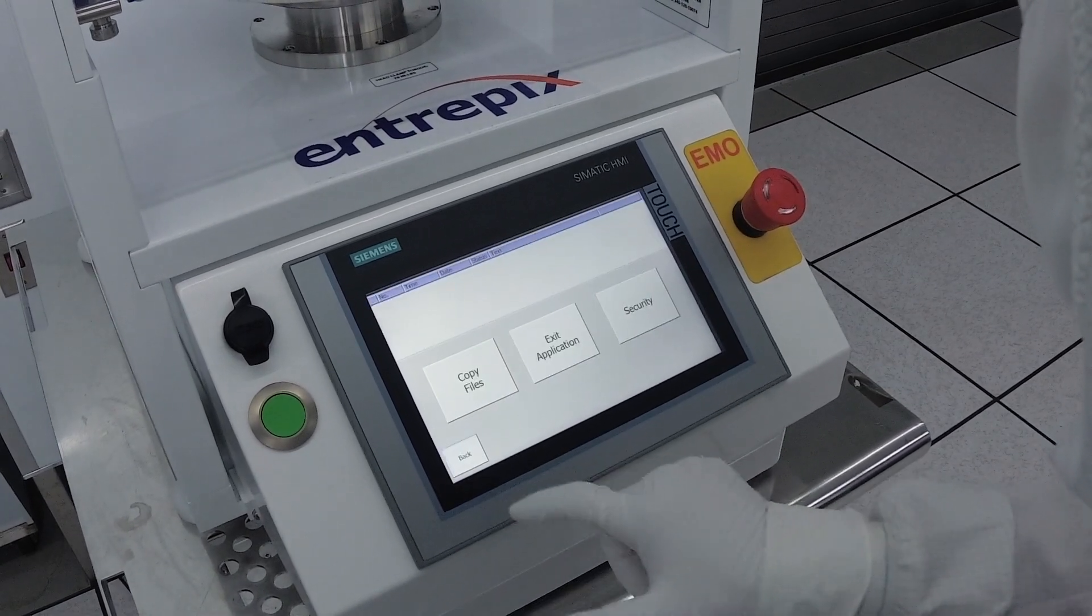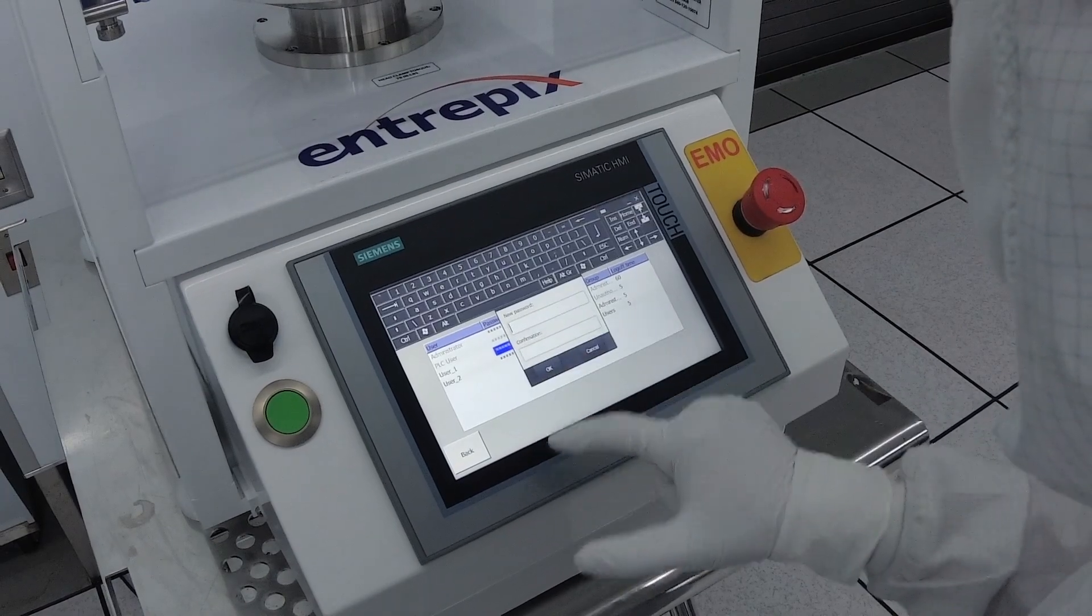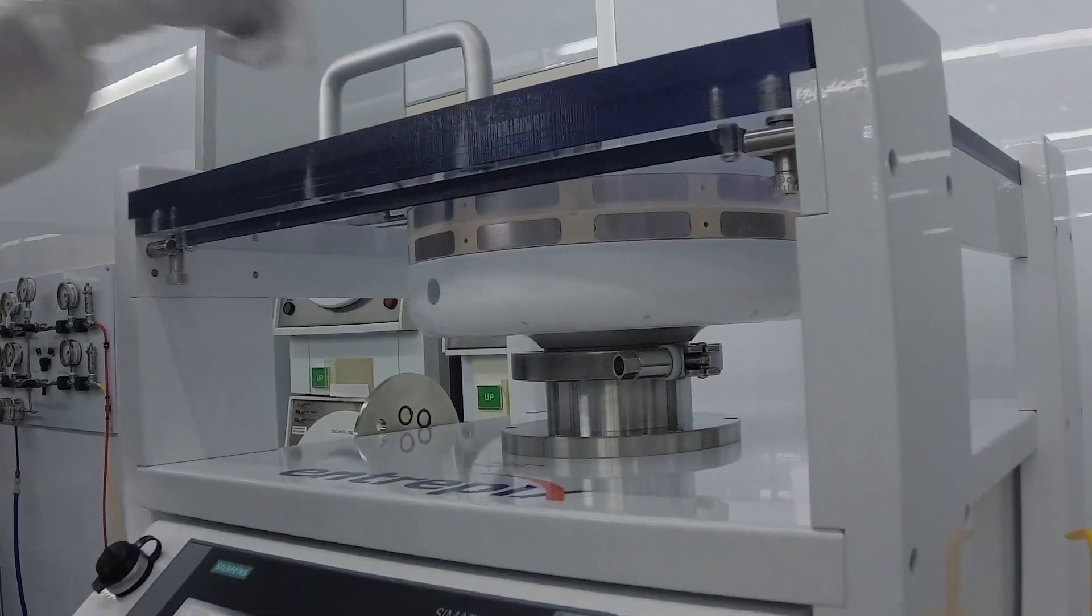This feature is available only when logged into the Head Tester as an engineering level user, preventing untrained and unauthorized personnel from damaging heads by manually changing solenoid states.